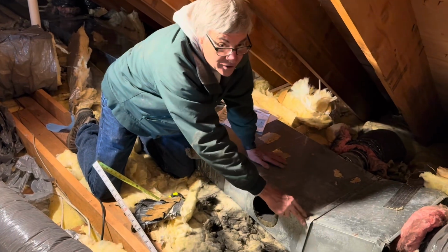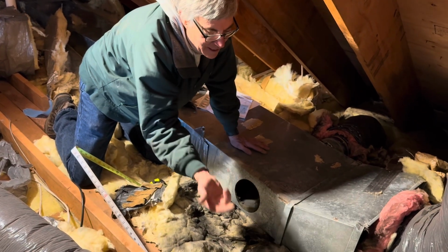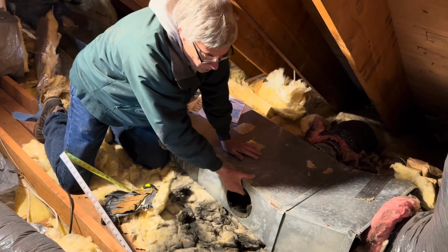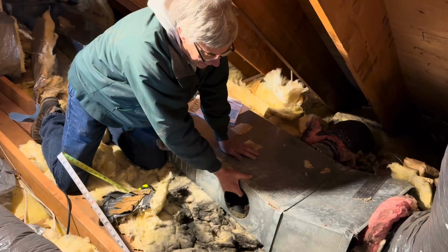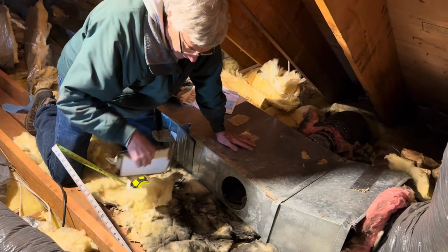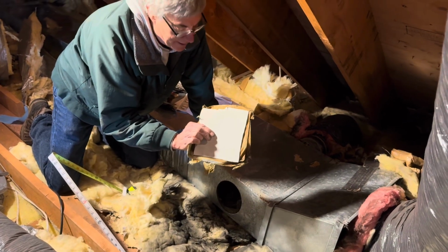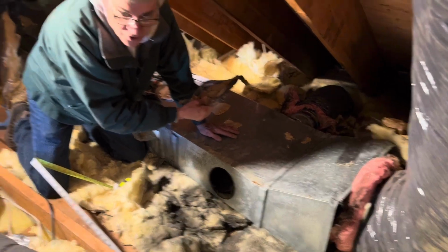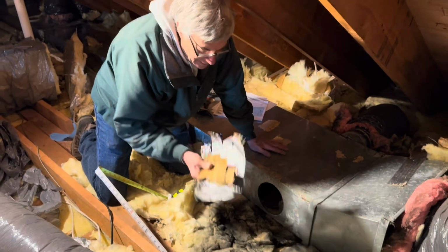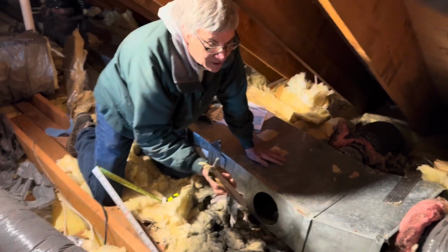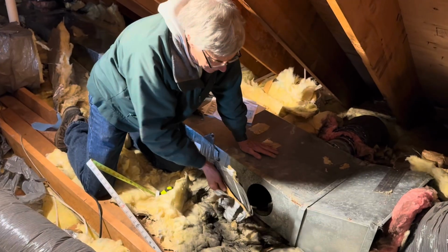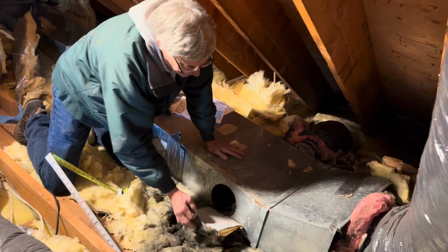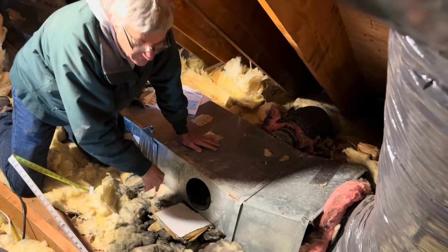We're going to seal this, and we're going to stop the loss and keep it in the house and not in the attic. These holes were where a duct was originally connected, and somewhere along the way, some rocket scientists had the idea that they were going to take this duct off to give more air someplace else, where it would never go. And they took the duct that was feeding probably the closet or something else, and they put this over it. Well, we know that didn't work very well because the tape dried out, the thing fell off, and all the air leaked out of the house.